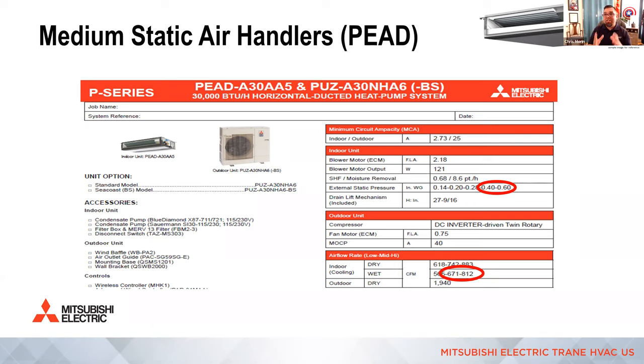So this is why the design for mid and high static is different compared to low static, because there's just not enough static pressure to go around a medium static and a medium fan on low static air handlers. High static, we can abide by those duct design rules. So in this example here, we're going to use 671 CFM at 0.4, and we would walk through the exact same process we just did. Or if we're using a high static air handler, it would be even higher choice. I'm going to show you that in a second. So you can see here, right off the submittal, 0.40 is a medium or medium high static, 671 with a wet coil on medium speed. That's what we would use for this particular 2.5-ton PEAD air handler.